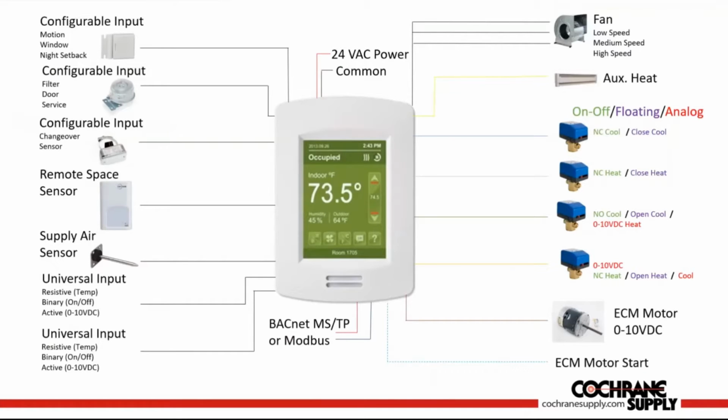The 8350 can be configured to operate a 3-speed fan or an ECM motor. The valve actuators at the installation could be on-off, floating, or 0 to 10 volt modulating. Don't worry, the 8350 room controller will work with them all. There's also a contact closure for supplemental or auxiliary heat. Just to reiterate, one part number has all of this configuration flexibility.